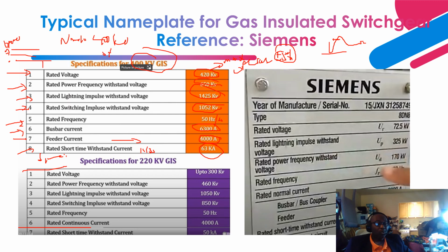Next, let's move on to another GIS that is rated at 220 kV, right? This GIS has been built with a rated voltage all the way up to 300 kV. So a lot of multiplier contingency has been built into this. Sometimes you can go more than 10%, depending on the customer's specification.